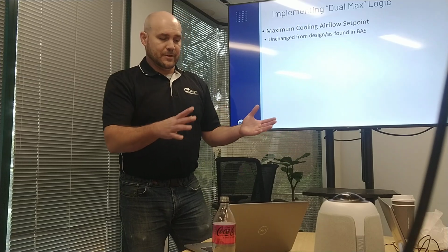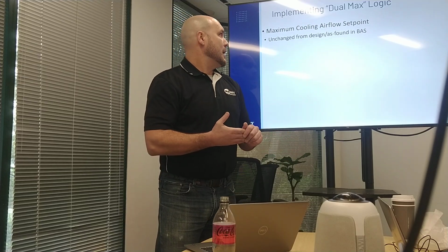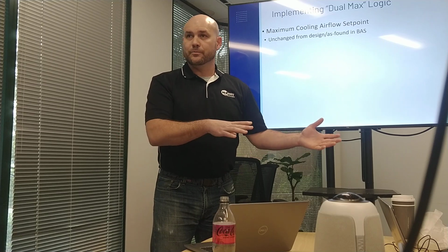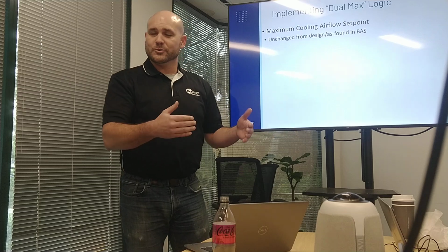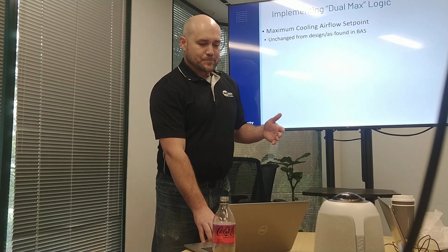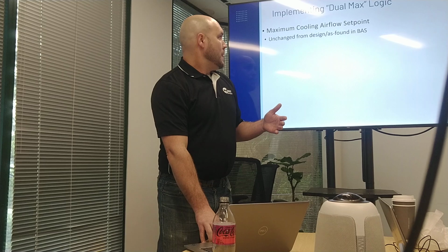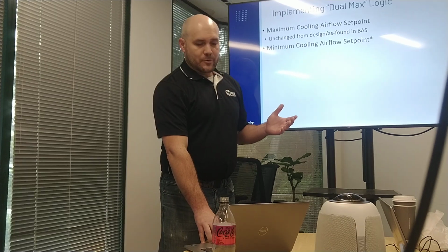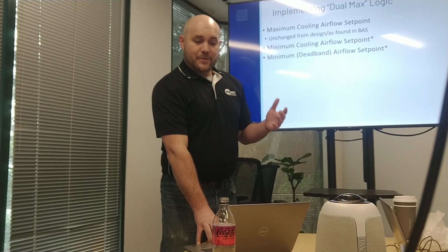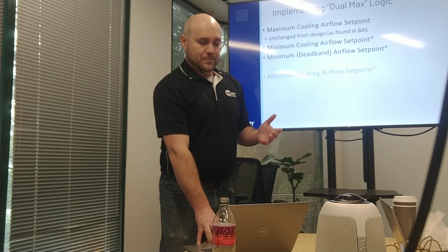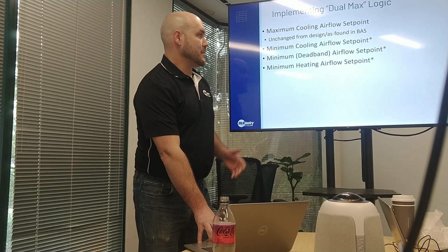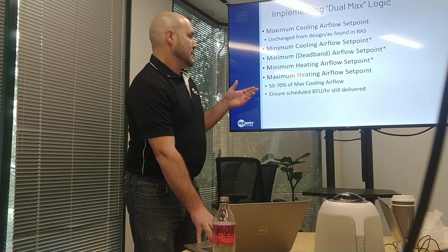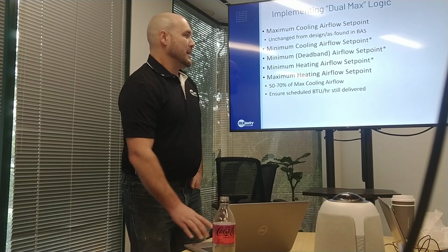To implement the dual max logic, compared to one of those earlier versions of logic, what does it take? You still need the maximum cooling airflow. That's going to be unchanged, whether it's the oldest school or old school version. Then you're going to need to define the minimum cooling airflow, the deadband minimum, the minimum heating airflow, and then you need to define the maximum heating airflow.